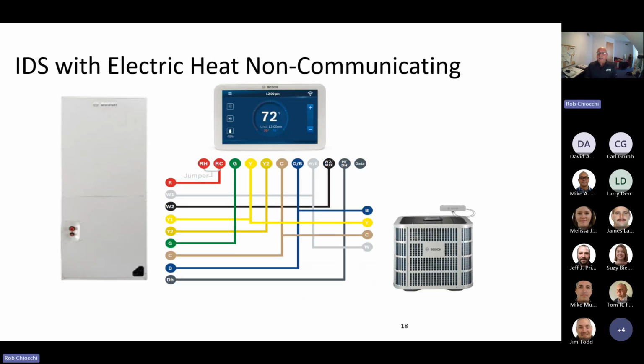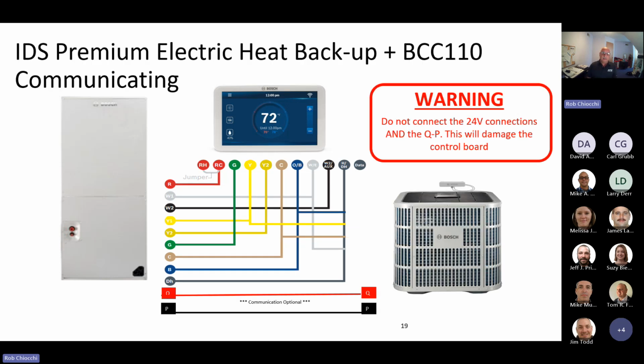Still able to use the BCC 110 and the IDS equipment as 24-volt legacy with 4 wires from the indoor unit to the outdoor unit and simple 24-volt wiring between the units. A great attribute the Bosch IDS systems have, but you will now have the option with the BCC 110 to wire between the indoor unit and the outdoor unit with 2 wires utilizing digital communication. This could be a great plus if you're going from a simple AC system to now a dual fuel system or a heat pump system, and you only have the 2 conductors going from the indoor unit to the outdoor unit.